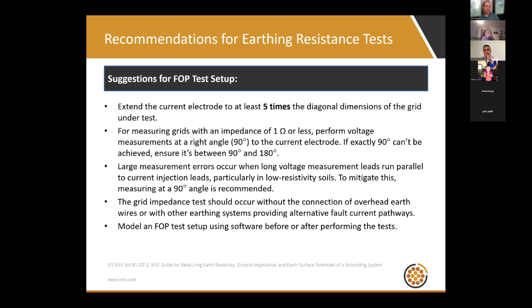So let's briefly list the recommendations for performing your Fall-of-Potential tests that you can take away with you in your engineering work. You should extend the current injection point to at least 5 times the diagonal distance of the grid itself, at least. If you expect a grid impedance measurement of 1 ohm or less, you should perform voltage measurements at 90 degrees with respect to the current electrode.